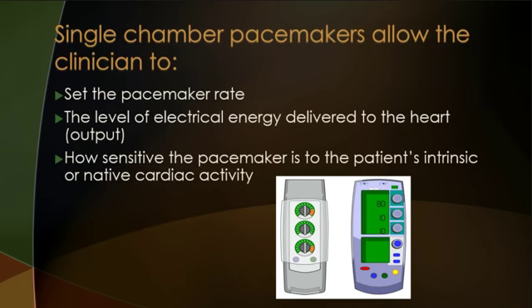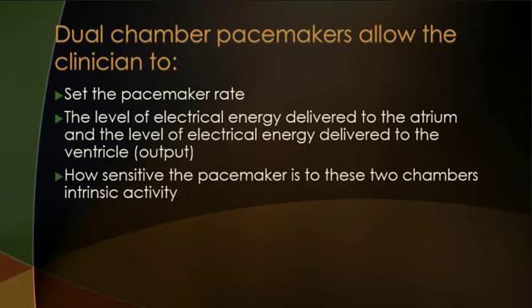Your single chamber pacemakers, they allow the clinician to set the pacemaker rate, set the level of the electrical energy delivered to the heart, and also how sensitive the pacemaker is to the patient's intrinsic or their own natural cardiac rhythm. Dual chamber pacemakers allow the clinician to set the pacemaker rate. They allow the level of electrical energy delivered to the atrium and the level of electrical energy delivered to the ventricle, both to be adjusted. And you can also tell the generator with a dual chamber how sensitive the pacemaker is to these two chambers' intrinsic activity.